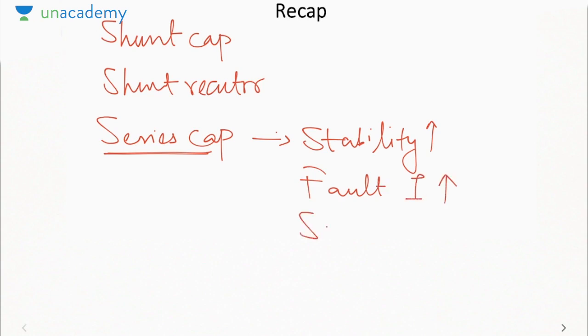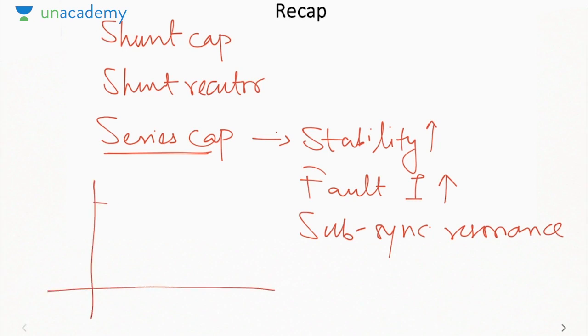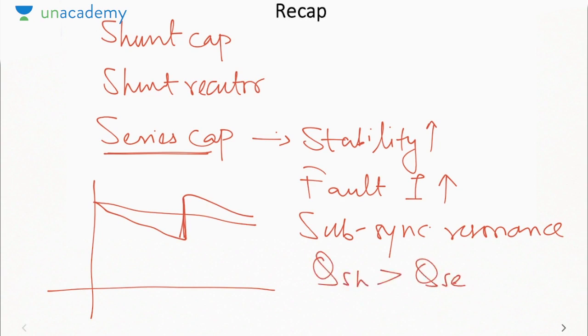But there was a problem of subsynchronous resonance, in which high torques can be produced which can damage the shaft of the machine. Then we compared the series and the shunt capacitor. We saw the voltage profile. With the shunt capacitor it was uniform. With the series capacitor it was like this. There is an abrupt change as soon as the capacitor is encountered. As well as we saw, for the same voltage improvement, Q shunt is greater than Q series.